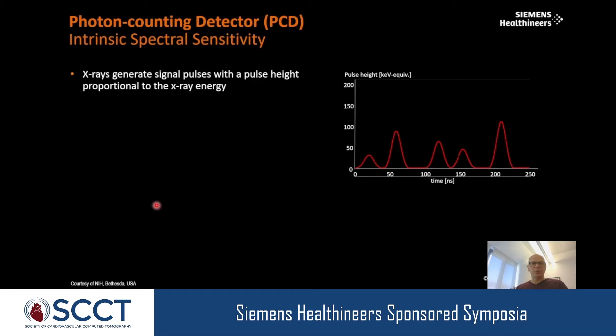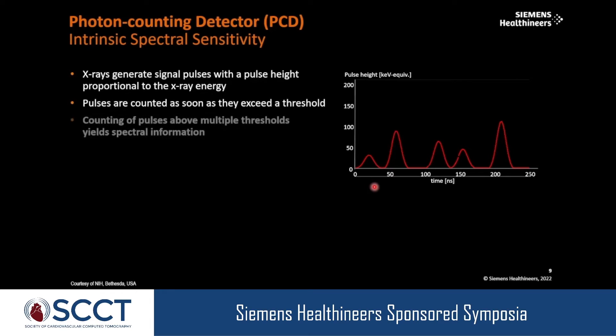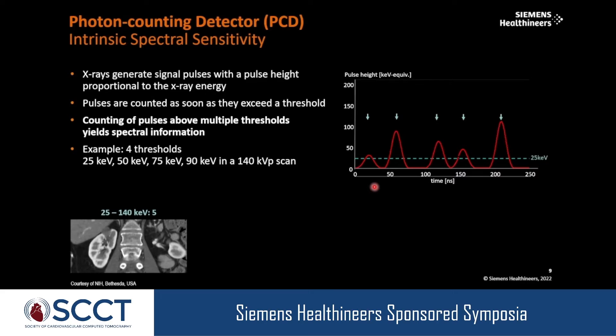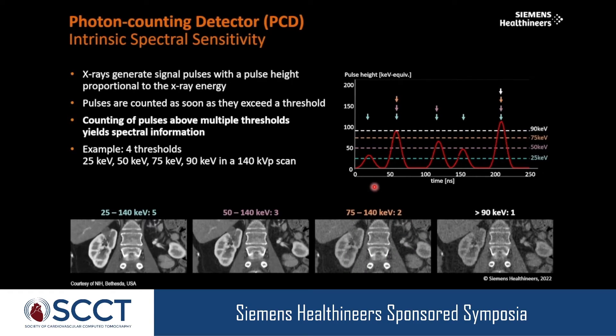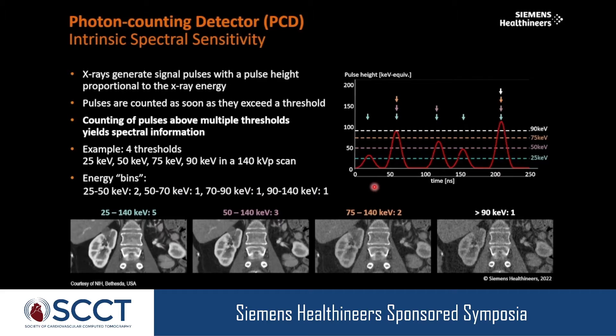To derive spectral information, the pulse height is proportional to the energy of each interacting quanta. Using thresholds in the electronics, depending on whether a peak exceeds a threshold, the photon is counted into the low, medium, high, or highest energy bin. After one scan, we don't have just one image at one energy level — we have four images at four different energy levels, which can be used for any kind of spectral processing.